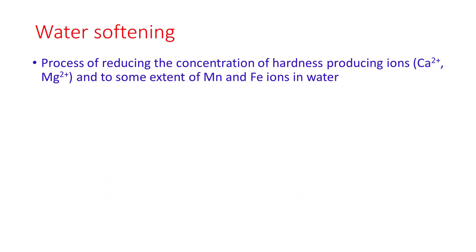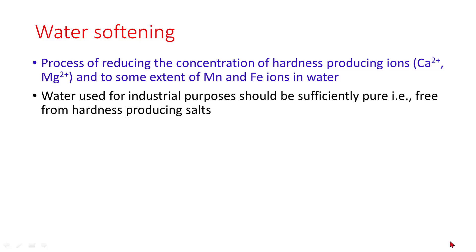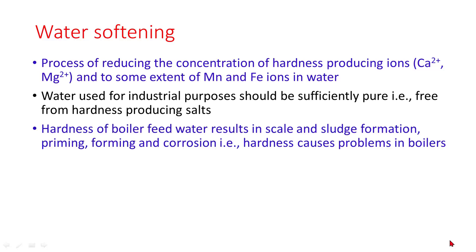Water softening is a process of reducing the concentration of calcium and magnesium ions, and to some extent of manganese and iron ions in water. Water used for industrial purposes should be sufficiently pure, that is free from calcium and magnesium salts. Hardness of boiler feed water results in scale and sludge formation, priming, forming, and corrosions. That means hardness causes problems in boilers.